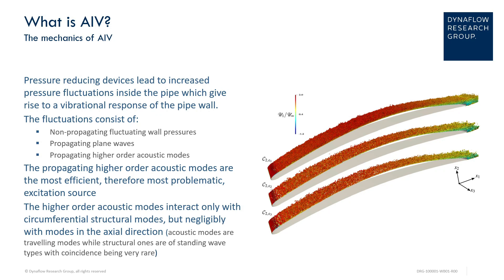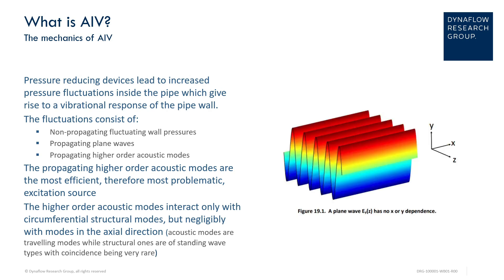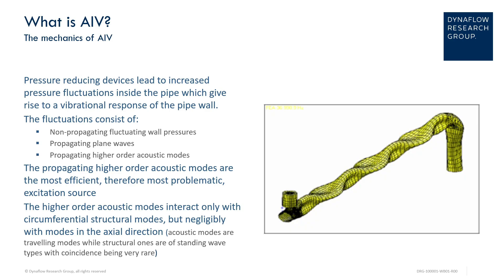The vibrational makeup of AIV consists of non-propagating fluctuating wall pressures induced by turbulence, causing an unsteady loading on the wall surface which in turn radiates noise; propagating plane waves that travel through the system; and propagating higher-order acoustic modes that excite the circumferential modes of the piping, also known as the flexural or breathing modes of the pipe. These latter fluctuations are the most efficient excitation source and therefore the most problematic.